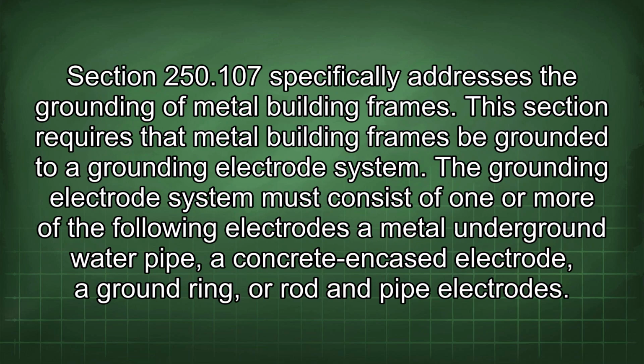Section 250.107 specifically addresses the grounding of metal building frames. This section requires that metal building frames be grounded to a grounding electrode system. The grounding electrode system must consist of one or more of the following electrodes: a metal underground water pipe, a concrete encased electrode, a ground ring, or rod and pipe electrodes.